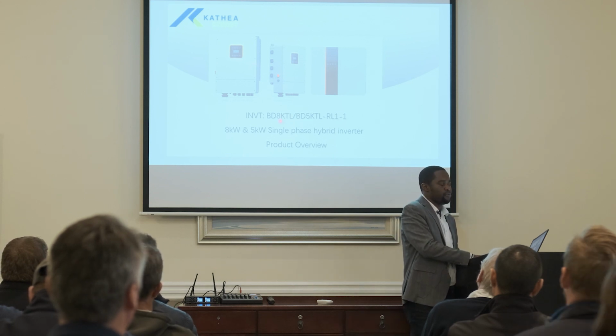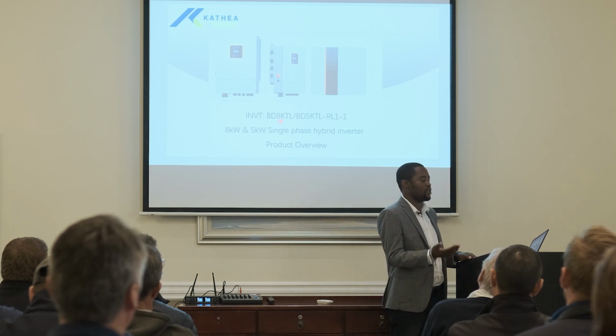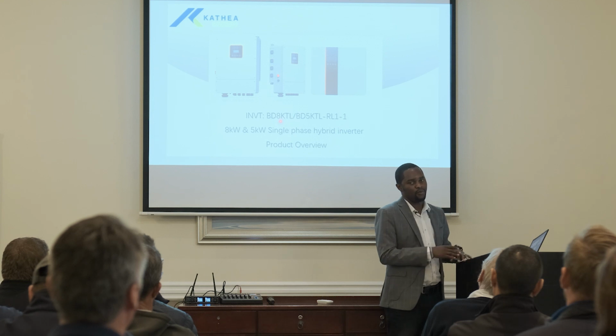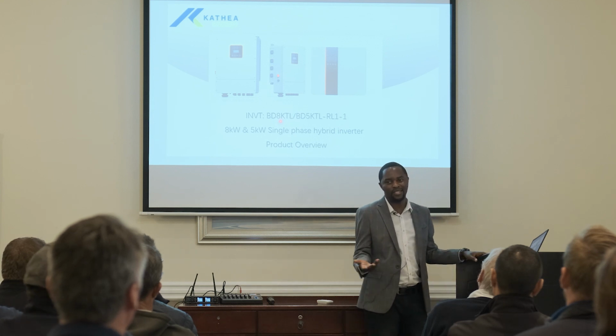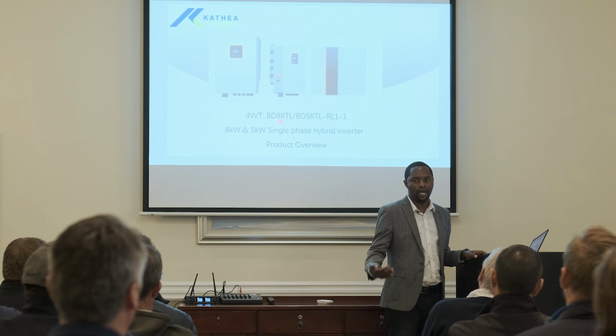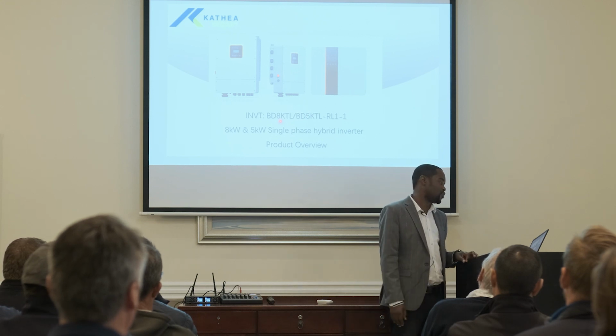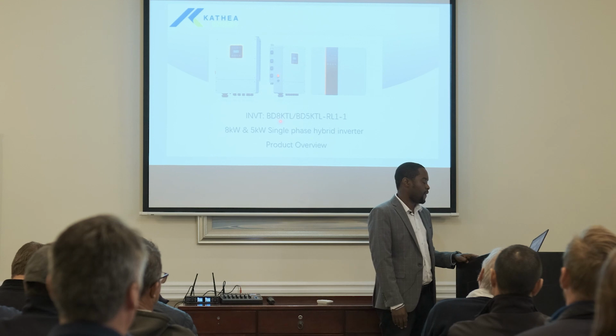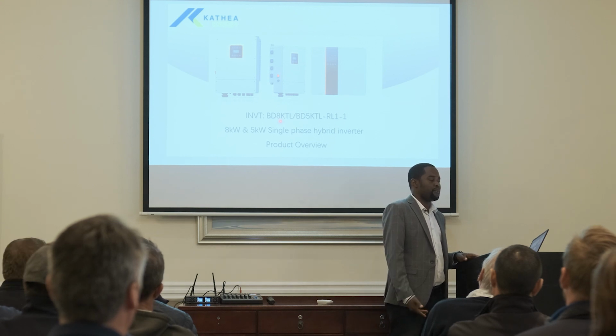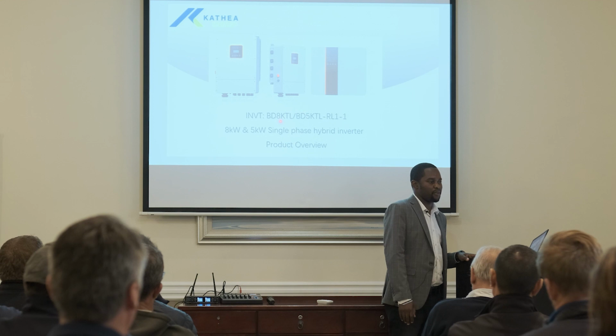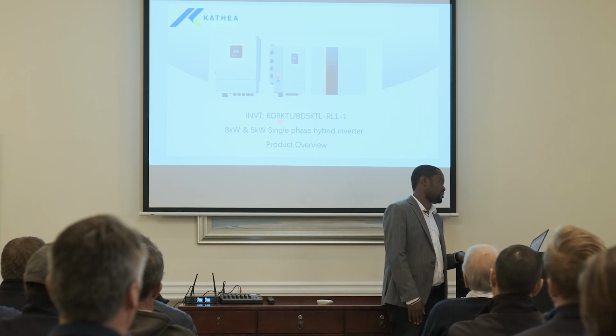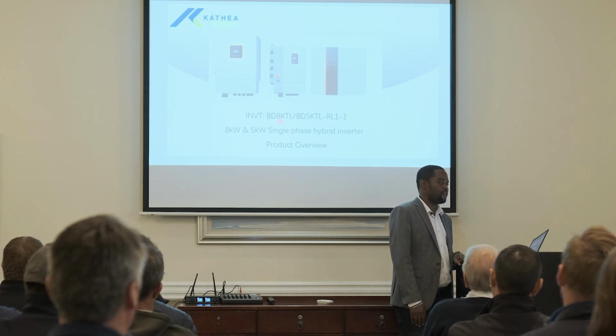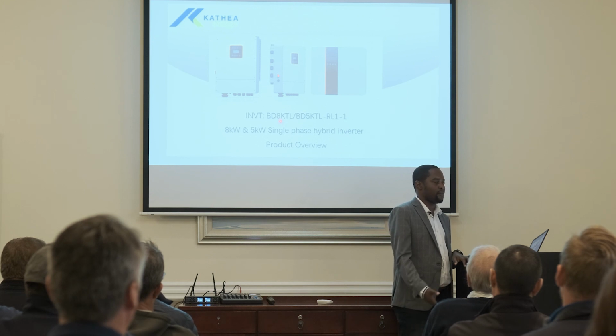The 8 kilowatt is a pure hybrid inverter. It can take low voltage batteries, any battery that is there. It can also work with lead acid and gel batteries. I'm not sure if anyone is still using those here, but if your client wants to buy those cheaper ones, you can definitely use those batteries on this inverter. With pure hybrid, you can feed back to the grid and get something from the grid, if Eskom is going to pay you back or at least give you a discount on your bill. You can feed your non-essential loads. You can do anything that any other pure hybrid inverter can do.